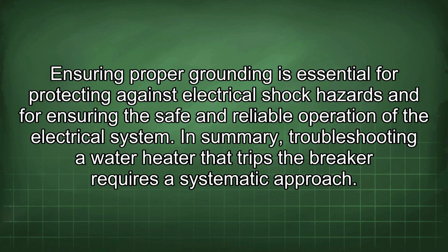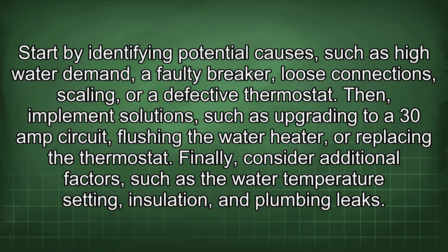In summary, troubleshooting a water heater that trips the breaker requires a systematic approach. Start by identifying potential causes such as high water demand, a faulty breaker, loose connections, scaling, or a defective thermostat. Then implement solutions such as upgrading to a 30-amp circuit, flushing the water heater, or replacing the thermostat. Finally, consider additional factors such as the water temperature setting, insulation, and plumbing leaks.